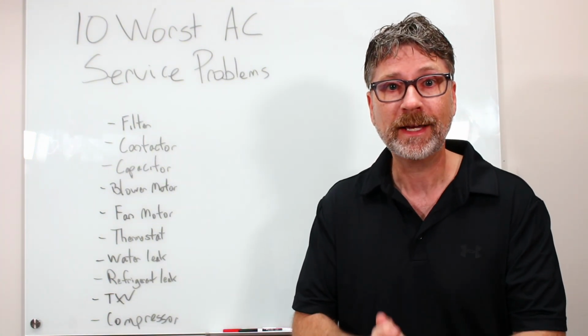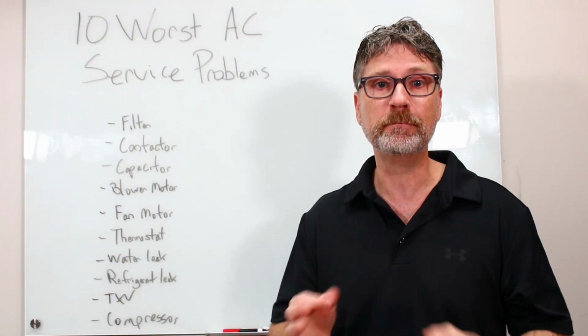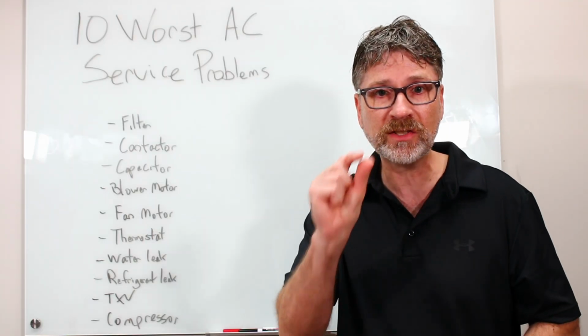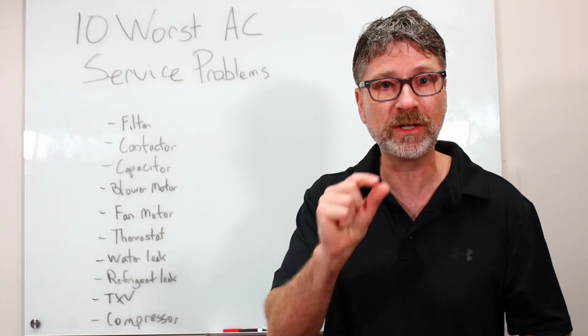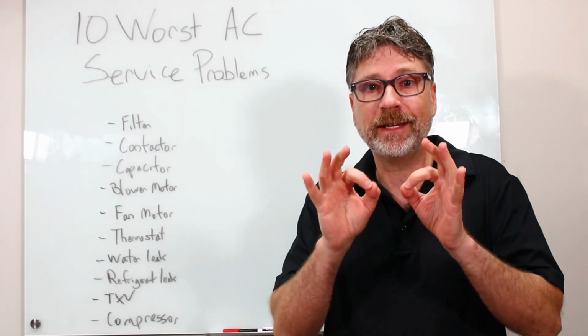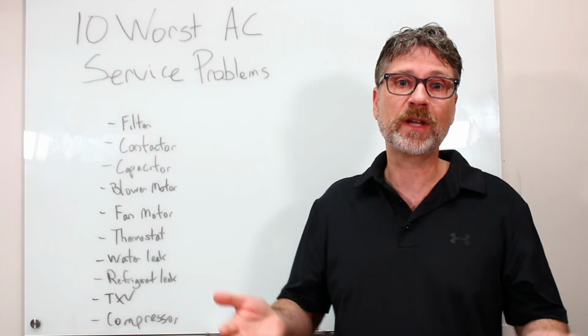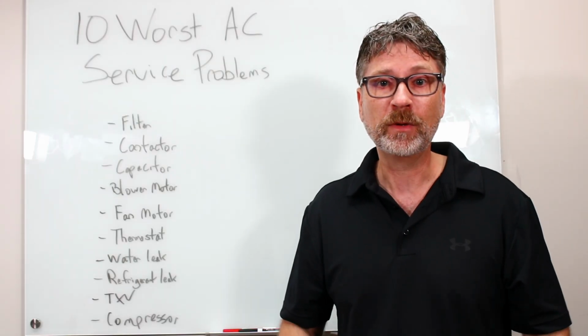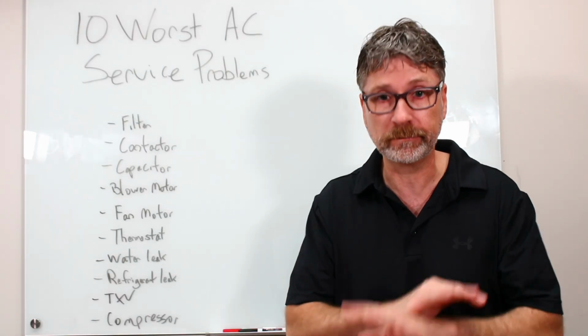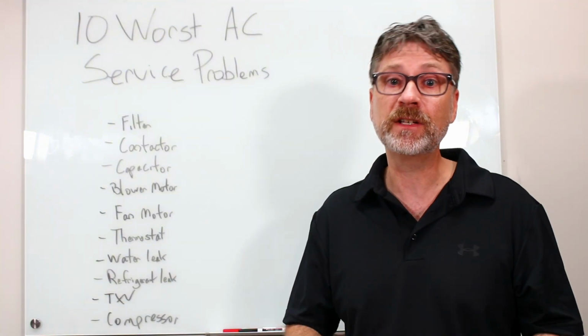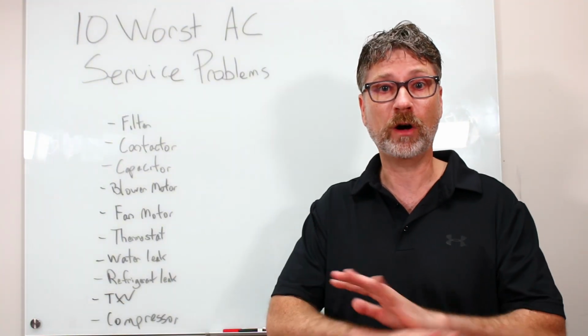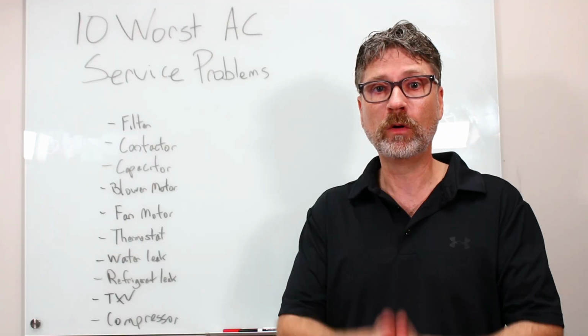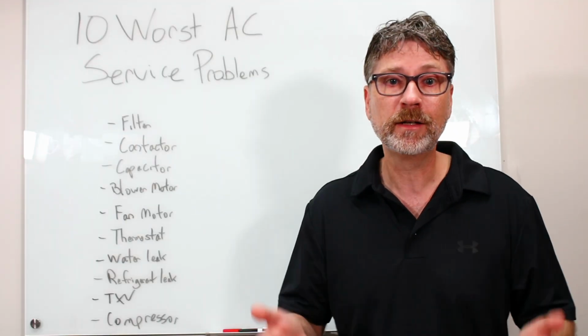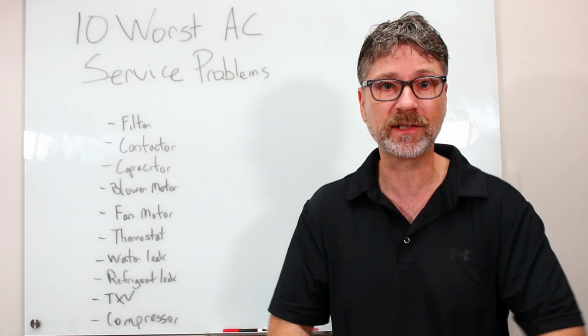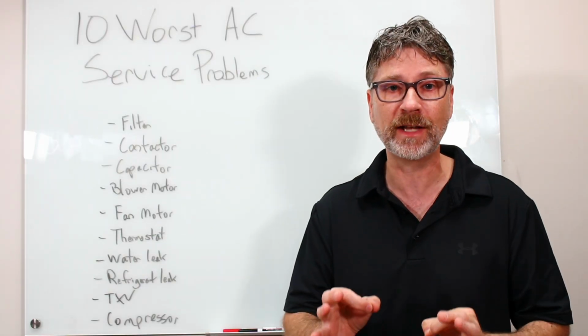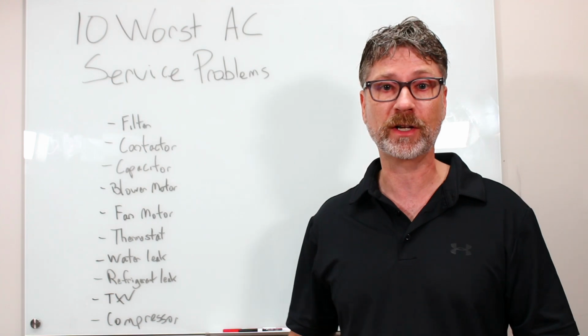Number 2. In every system, there is a refrigerant metering device that lets through just the right amount of refrigerant for each condition. Think small, tiny, adjustable valve. These can sometimes get stuck or plugged. When that happens, your system will run poorly or not at all. Replacing a TXV is also a big deal. It requires removing all of the refrigerant, removing the old valve, and brazing in a new one. Then, replacing the refrigerant, rebalancing the system, and starting it. This is a $1,000 or more sort of project.